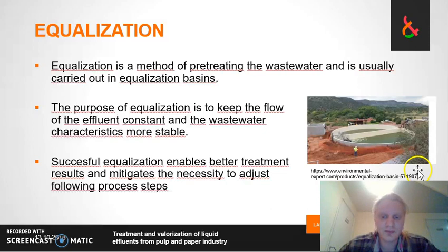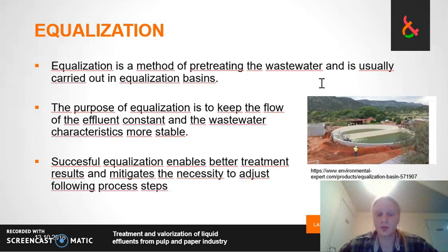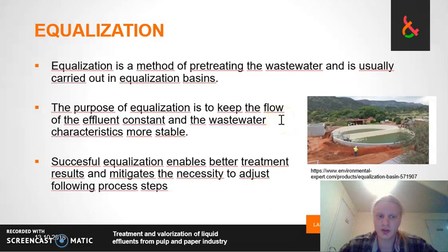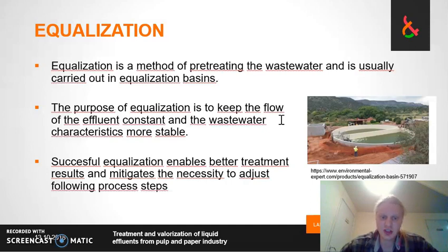The purpose of these equalization basins is to basically act as a buffer before the actual wastewater treatment. They aim to keep the flow of the effluent constant and the wastewater characteristics more stable, so that the input to the aeration tank could be as stable as possible. A successful equalization enables better treatment results and mitigates the necessity to adjust the following process steps.